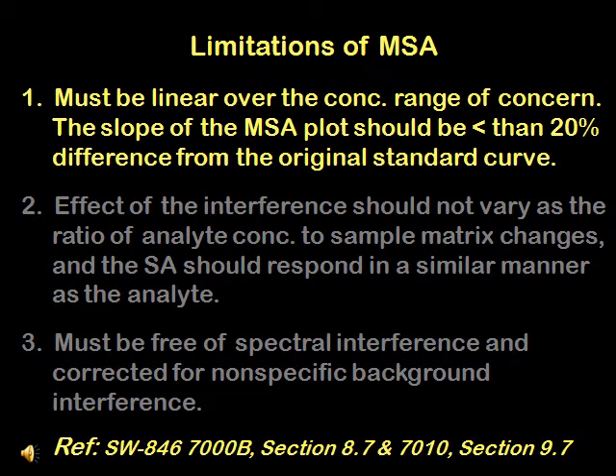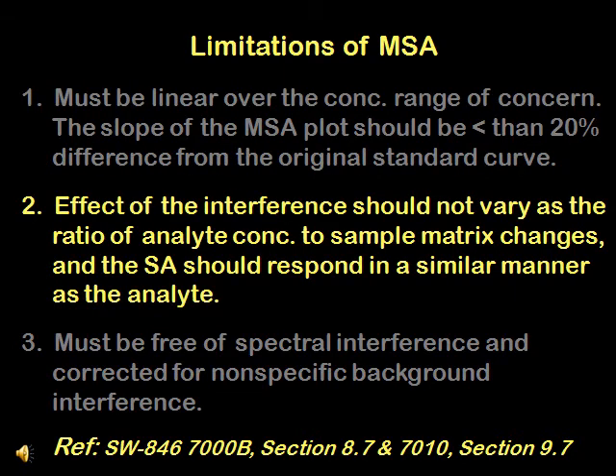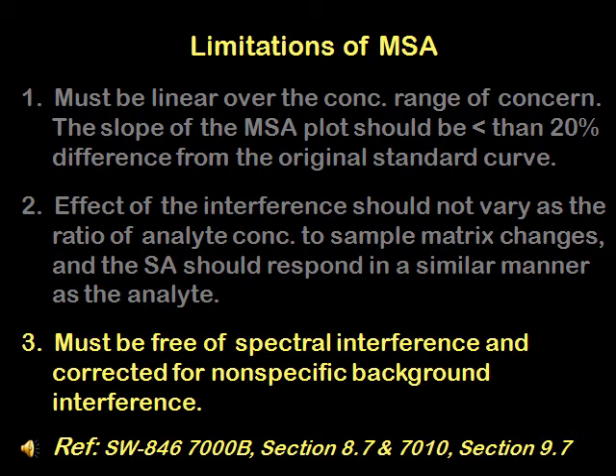There are limitations to the method of standard additions. First, it must be linear over the concentration range of concern. As previously stated, the slope of the MSA plot should be less than 20% difference from the original standard curve. Second, the effect of the interference should not vary as the ratio of analyte concentration to sample matrix changes, and the standard addition should respond in a similar manner as the analyte. Third, the instrument must be appropriately set up to be free of spectral interference and corrected for nonspecific background interference.